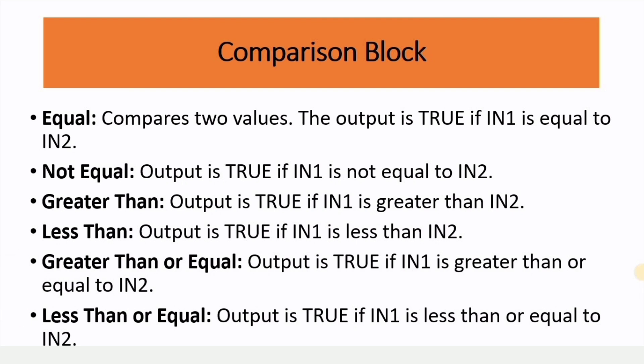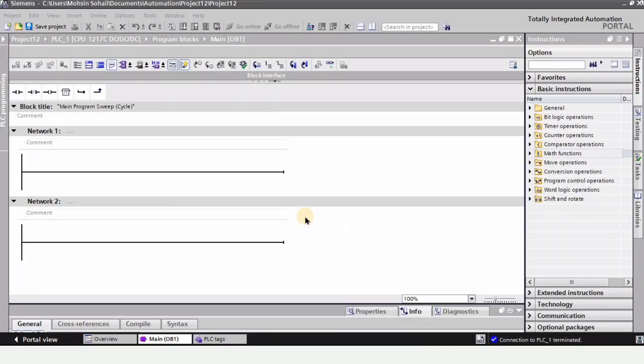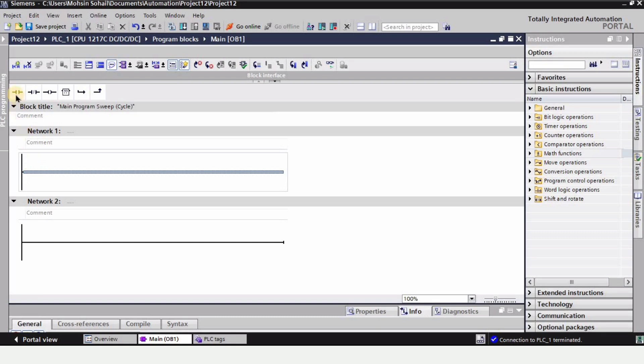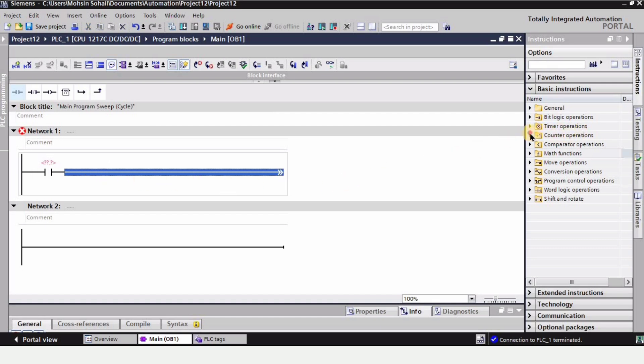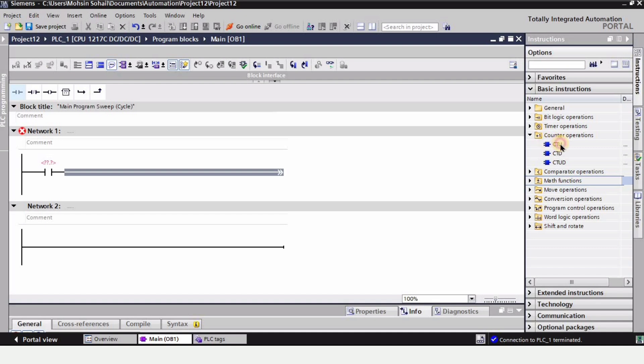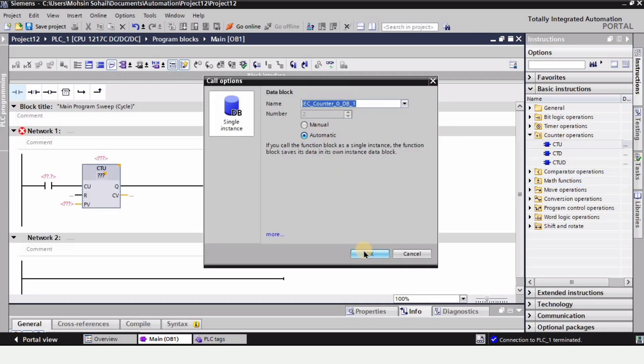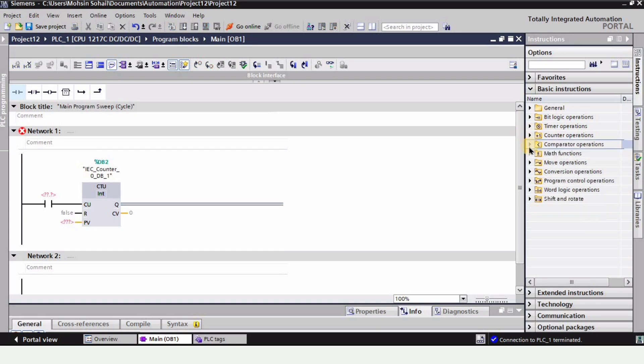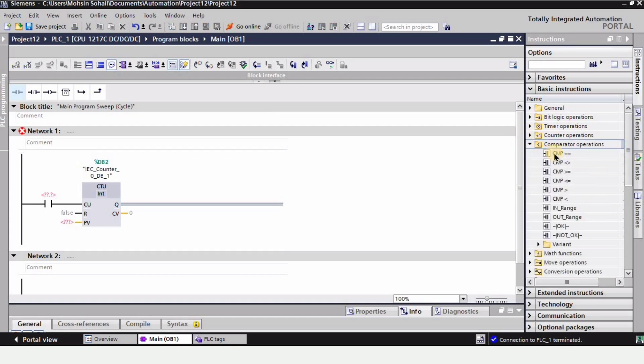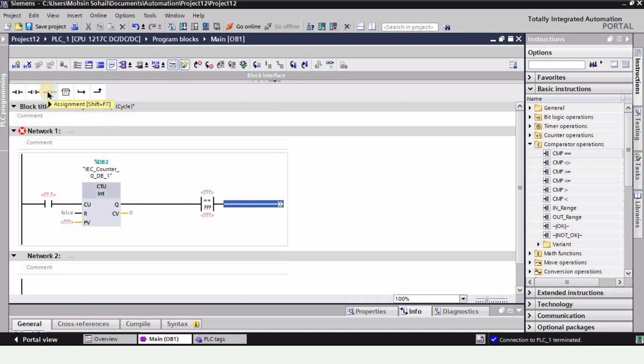Now let's see how we can configure these instructions in the TIA portal software. I'm going to select this line and place a normally open contact, which will work as the input switch. Then I'll select this line and add a count up counter — I'll double click on CTU and click OK. So the count up counter is placed. Then I'll select this line and from the comparator operators dropdown, select the first one, which verifies the equality of two values. Finally, I'll place the output.